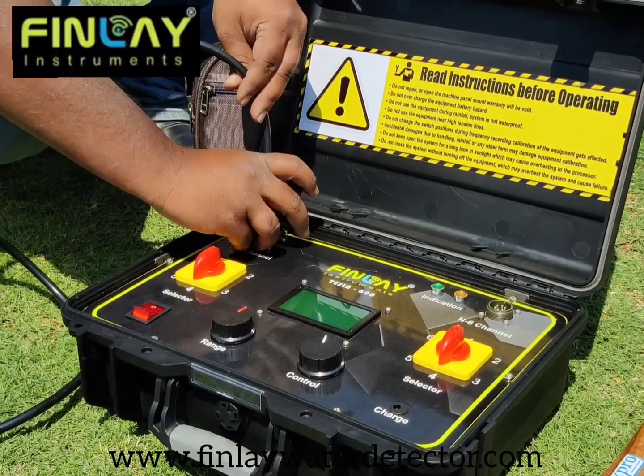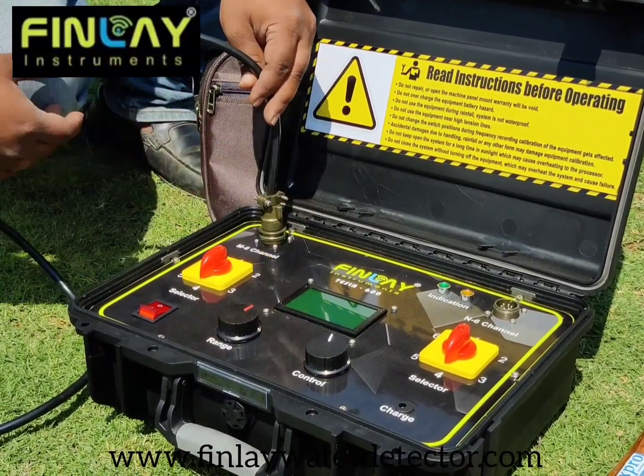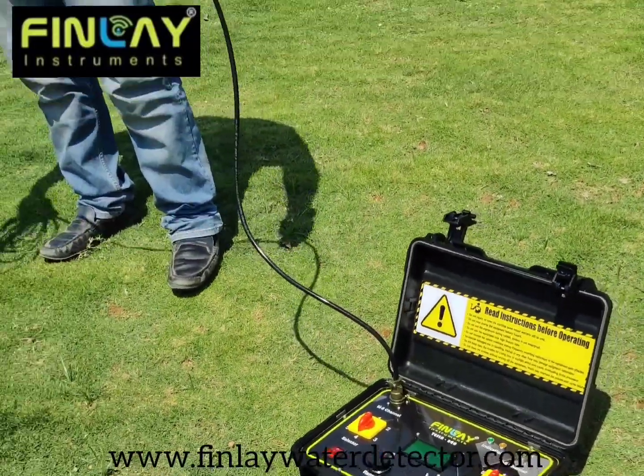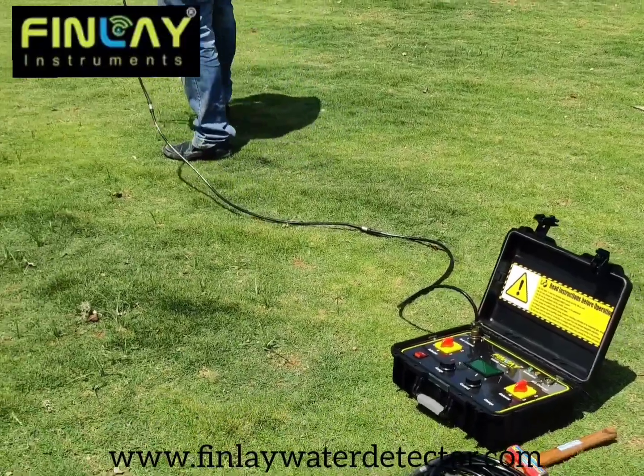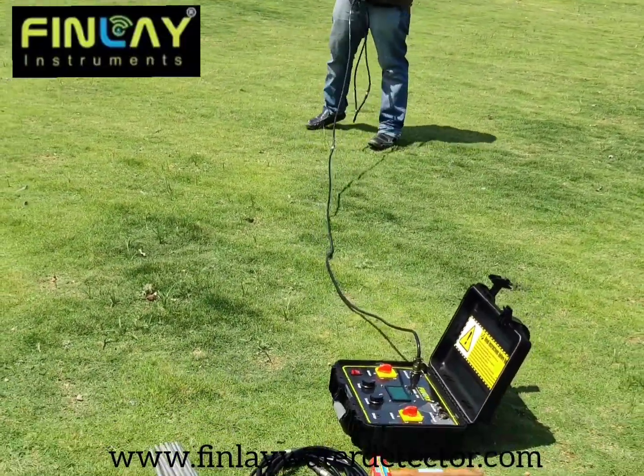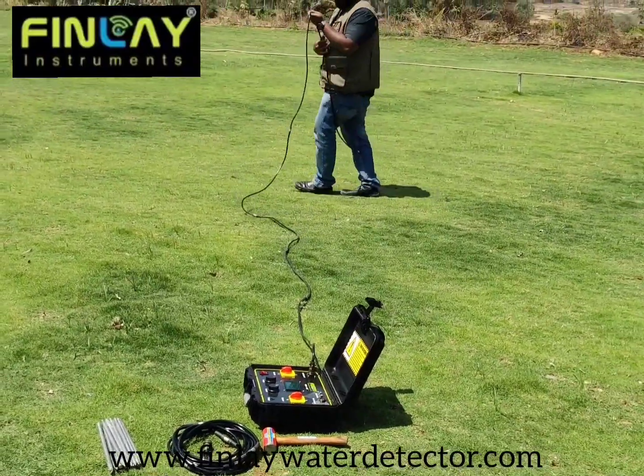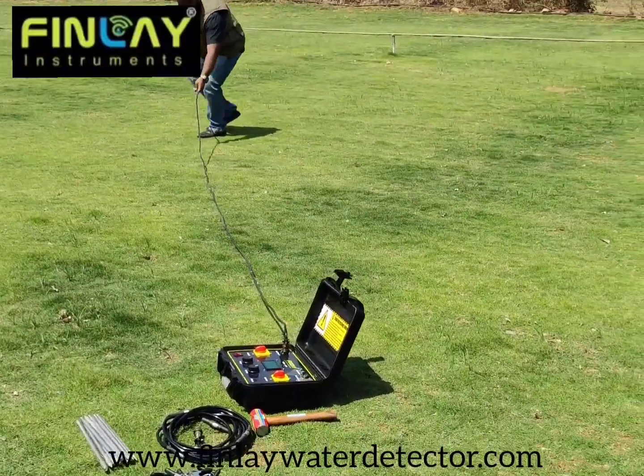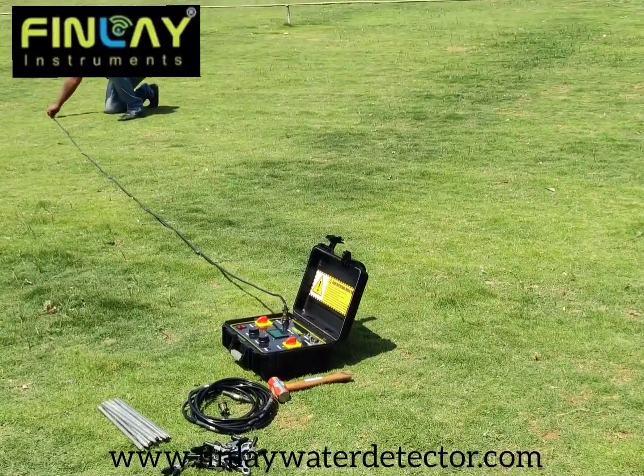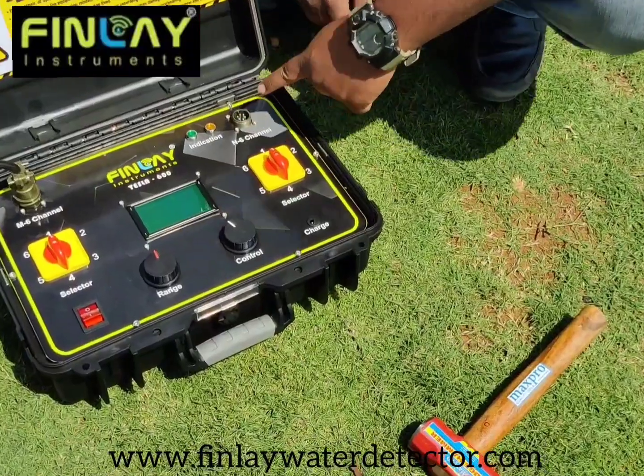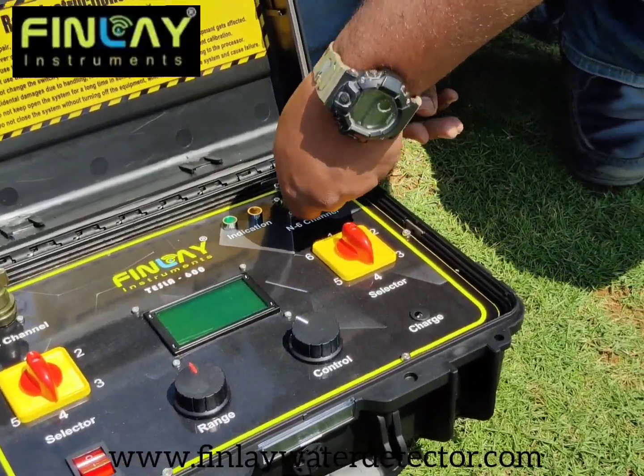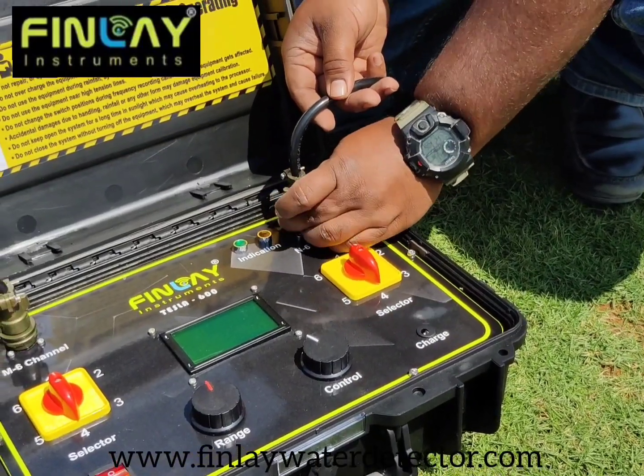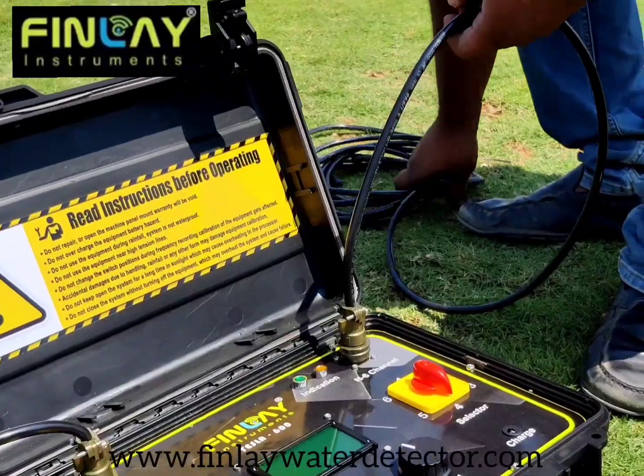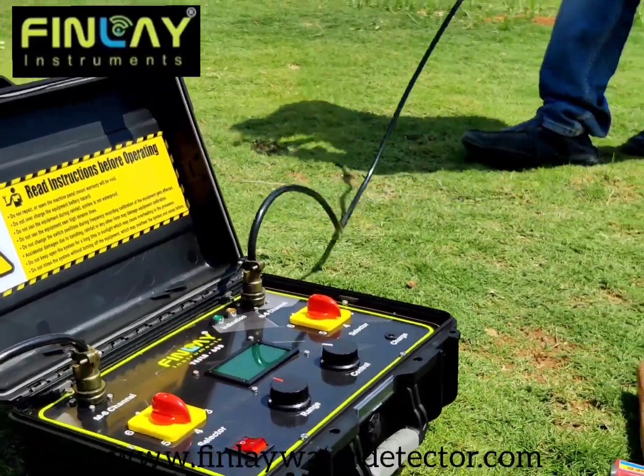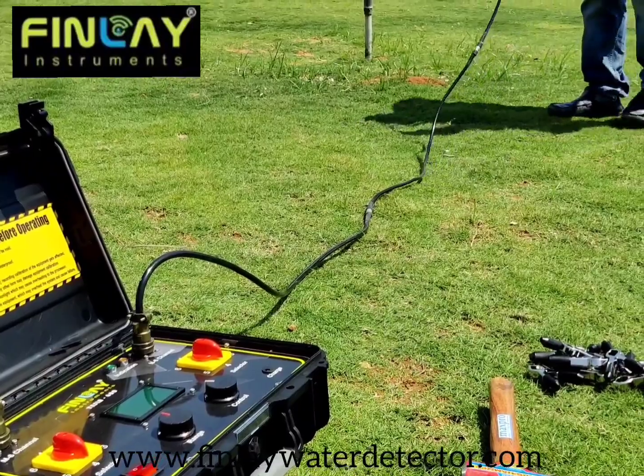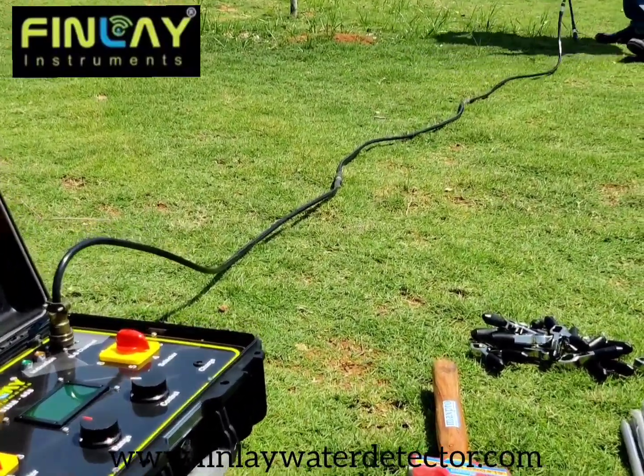After connecting the cable to the mainframe system, the transmission line should be spread on the ground vertically towards the left hand side from the point to be detected for 6 meters. The same way, we need to connect the receiver line to the mainframe system. After connecting the cable to the mainframe system, the receiver cable should be spread towards the right hand side from the point to be detected vertically.